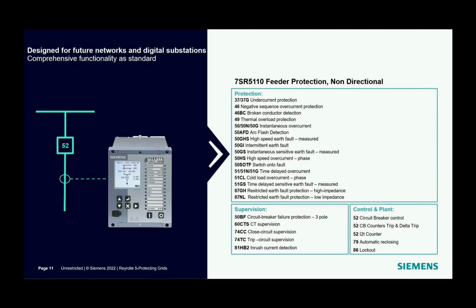87GH stands for high impedance, and 87NL stands for low impedance, depending on the application required. So you can apply both high impedance and low impedance restricted earth fault. You can just choose. To complete your application, all Reyrolle 5 devices have the option for direct arc flash detection inputs with high-speed tripping contacts for fast clearance when arc faults are detected in your switchgear. And again, all Reyrolle 5 devices have the option for direct temperature sensor inputs, and they are connected to sensors in the plant.